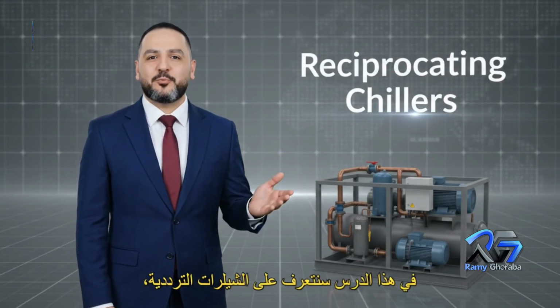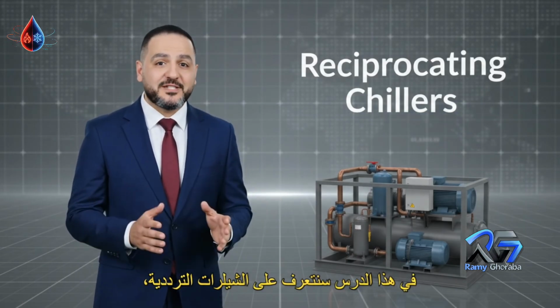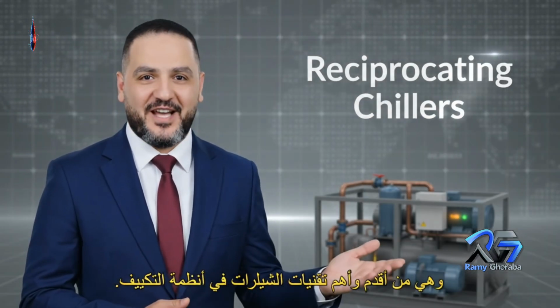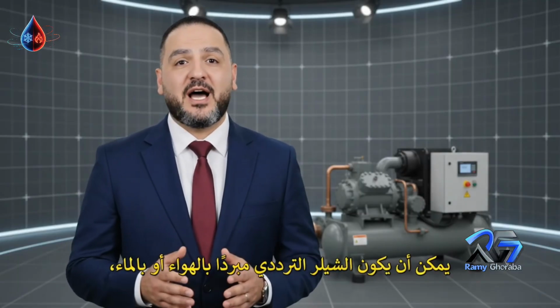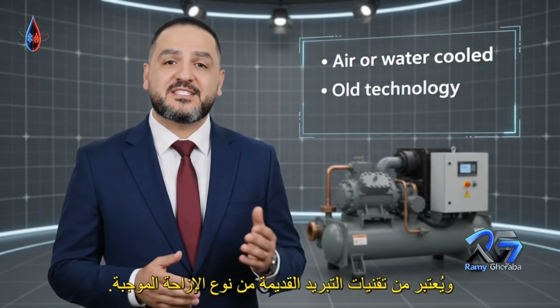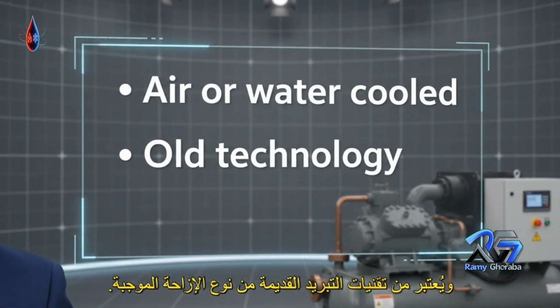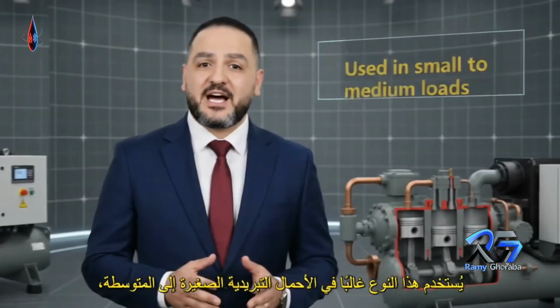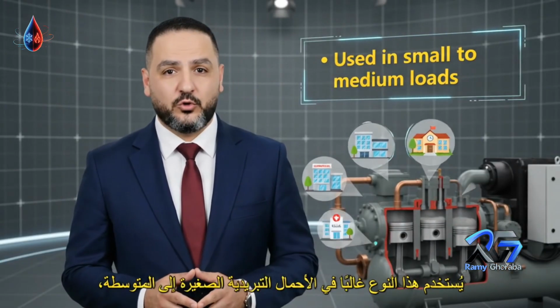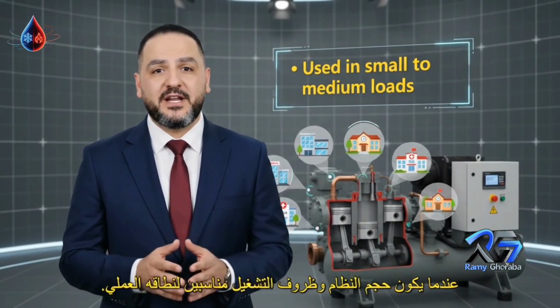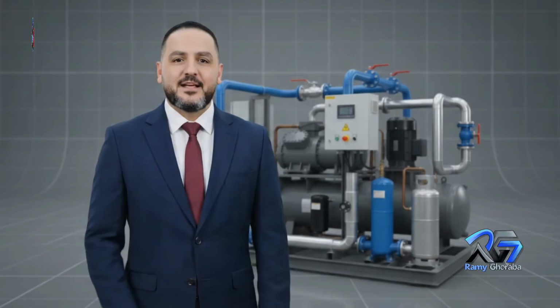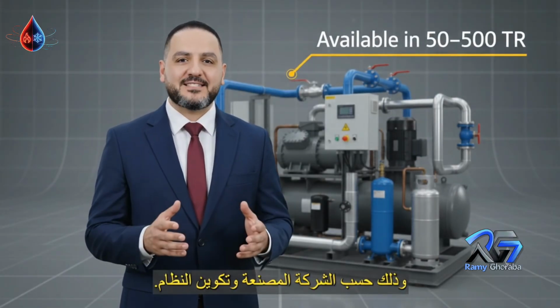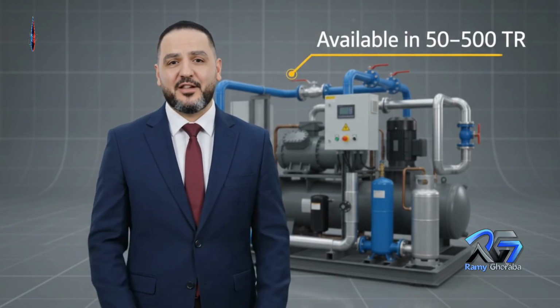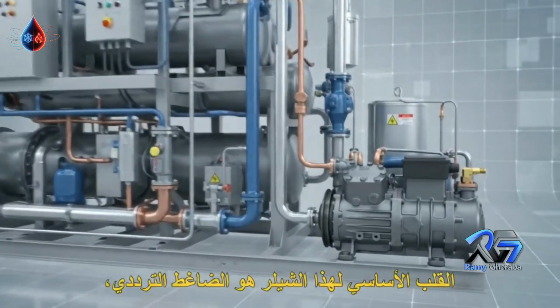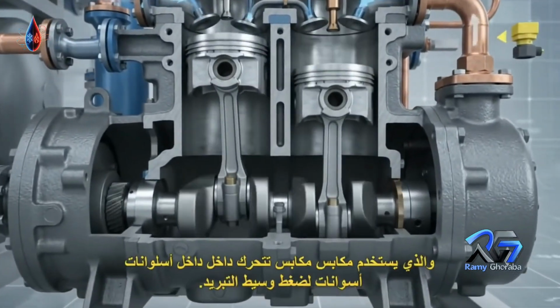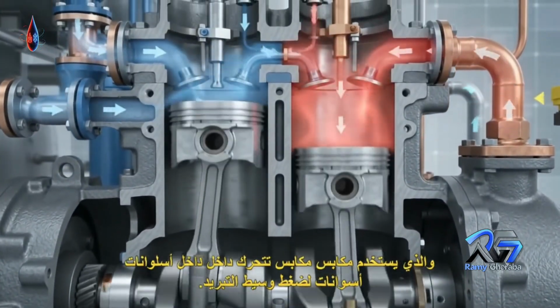In this lesson, we'll explore reciprocating chillers, one of the oldest and most important chiller technologies in HVAC. A reciprocating chiller can be either air-cooled or water-cooled, and it is considered an older positive displacement refrigeration technology. This type is mainly used for small to medium cooling loads, where the system size and operating conditions fit its practical range. Typically, reciprocating chillers are available in capacities from about 50 to 500 TR, depending on the manufacturer and system configuration. The heart of this chiller is the reciprocating compressor, which uses pistons moving inside cylinders to compress the refrigerant.